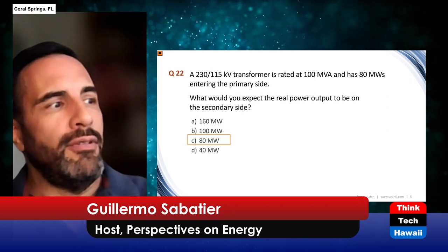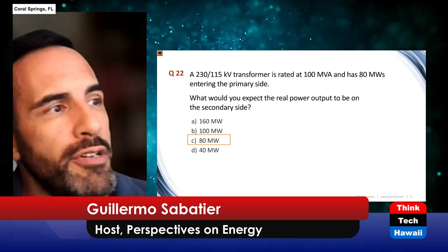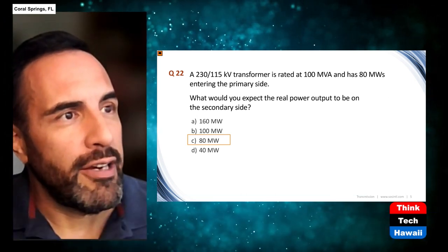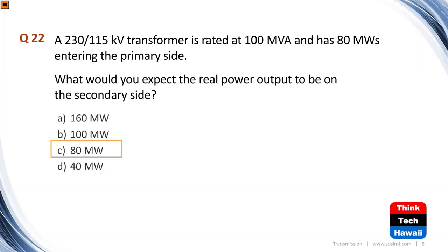So that's what they're asking, what would you expect the real power output to be on the secondary side. They're saying 80 megawatts entering the primary side, so you're going to have 80 megawatts going on the other side. Granted, you're not accounting for losses. In some cases you have very minimal losses in these transformers, but in this case they're neglecting them.